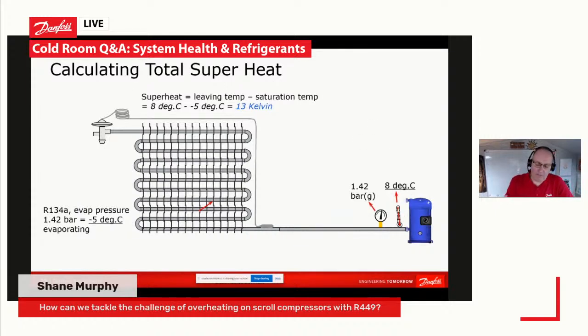A lot of our machines are okay for a return gas temperature of 20 degrees C, depending on the envelope of the machine. But basically, you've got to keep that machine operating within its envelope, its happy place, as I call it. If you let it outside of that, then the discharge temperature will increase very, very rapidly. The other thing also with the scroll, if you run it short of gas, then the discharge temperature will increase very, very rapidly. So you've got to be very careful during the commissioning process, during the charging process, that you are not letting that discharge temperature get too high.